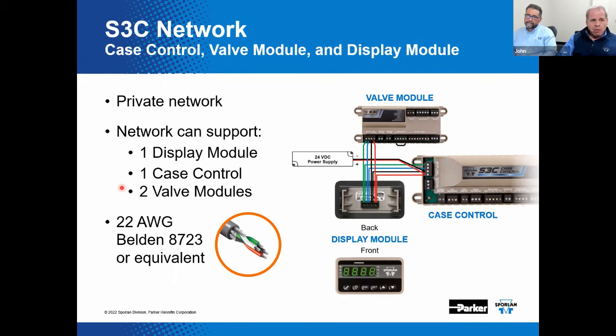And we talk about them being wired with 22 AWG, and we specify Belden 8723 or equivalent as far as the wire is concerned. We have an exploded detail here of the twisted pairs with the shielding that comes around it. Right. Now, Belden specified 2 twisted pairs with that shielding. Who or what is Belden? John, do you know? Belden is probably the big name in cable manufacturing out there. Been around for a number of years, and I don't have any idea how many different types of cable and products, but they are kind of the industry standard. So it's typical to cite a product of theirs and say their product or equivalent. Okay, so it's a standard for specifying wires or cable.